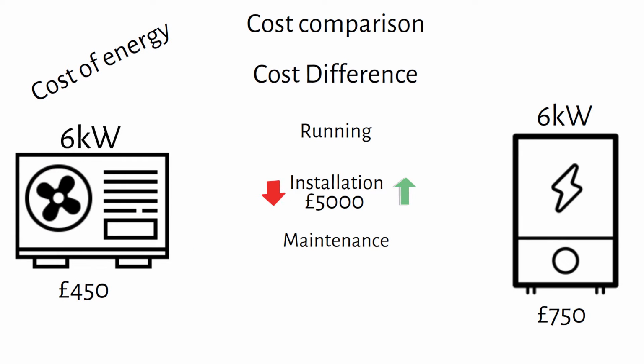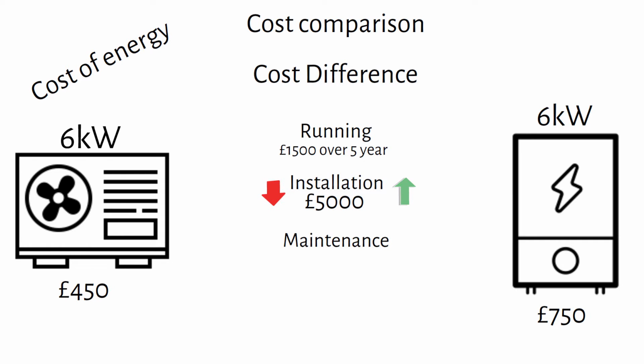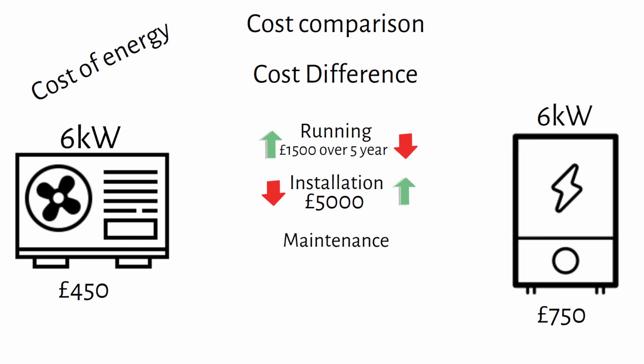If that figure is to increase, Bob will still be paying more having an electric boiler installed, but the comparison will be the same. Because the COP on the air source heat pump will always be around 3, and the electric boiler will always be between 1 to 1.5.